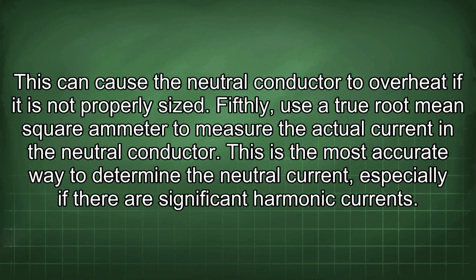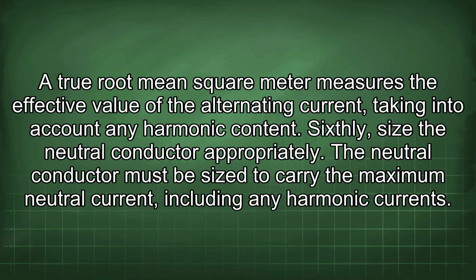Fifthly, use a true root mean square ammeter to measure the actual current in the neutral conductor. This is the most accurate way to determine the neutral current, especially if there are significant harmonic currents. A true root mean square meter measures the effective value of the alternating current, taking into account any harmonic content.